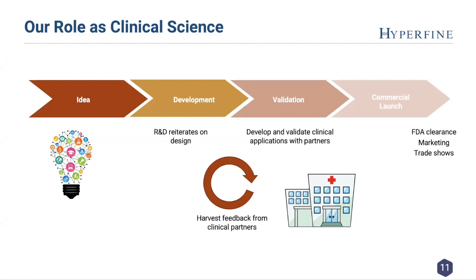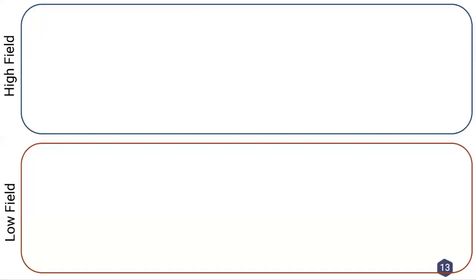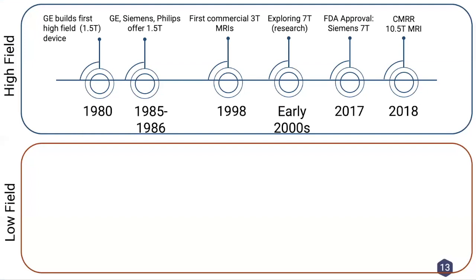Moving on to low field MRI, this is closely related to Hyperfine, which uses a low field magnet. I'd like to thank my colleague Samantha Bai for making this slide. While high field MRI has been on a steady march the last three or four decades, constantly increasing in capability and field strength, the first 1.5 Tesla was in 1980, and GE, Siemens, and Philips all offered it by the mid-80s. Then 3T came onto the scene in the 90s, 7T in the 2000s, and now Siemens has an approved 7T for certain indications, with research marching even higher, above 7 Tesla to 10.5 Tesla.